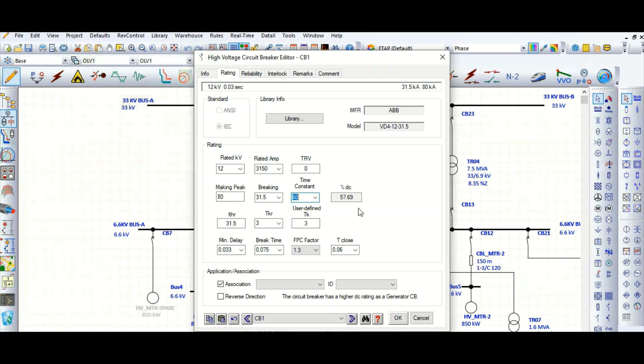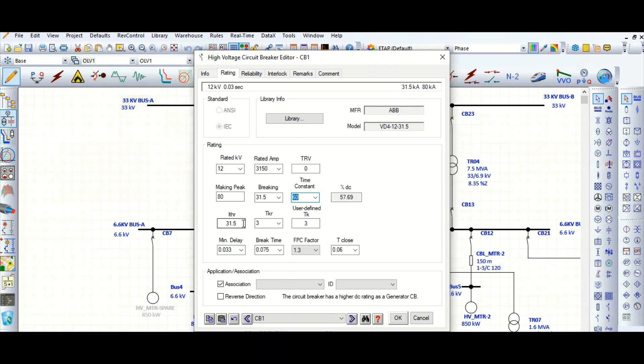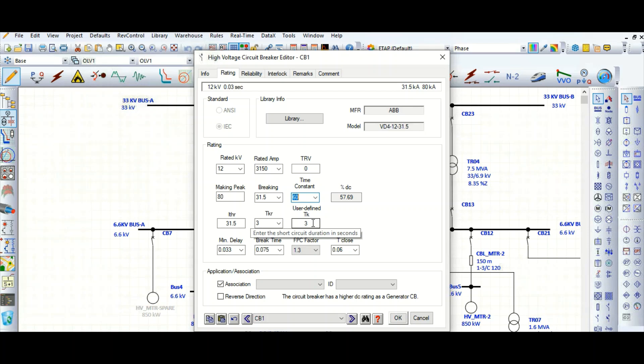This is the percentage DC component. Here is the thermal current — the thermal-related short time withstand current, which is 31.5 kA, and the rated short time is 3 seconds. That means the circuit breaker can withstand 31.5 kA rms for up to 3 seconds — this is the short circuit withstand capability.